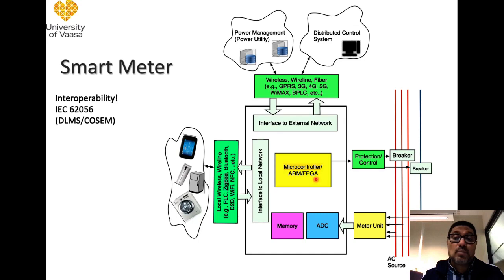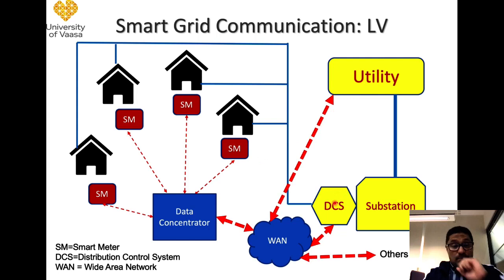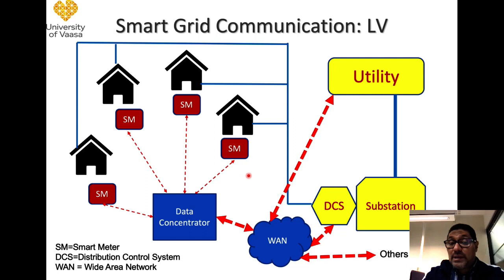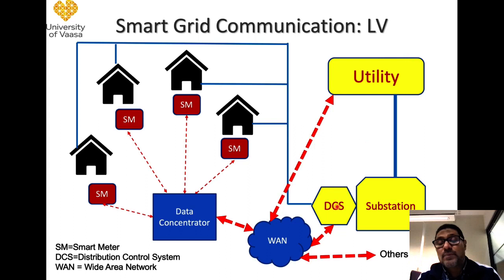In a more general structure, each smart meter should be able to communicate with the utility or the distribution control system. To have a more efficient network, it would be better to have a data concentrator. The data concentrator collects data from many smart meters — especially for small customer sites — and connects that data to the wide area network, which then goes to the utility and the distribution control system to manage power distribution.